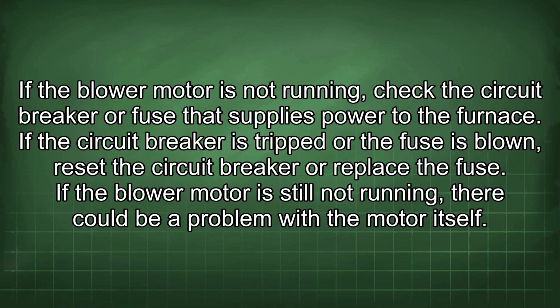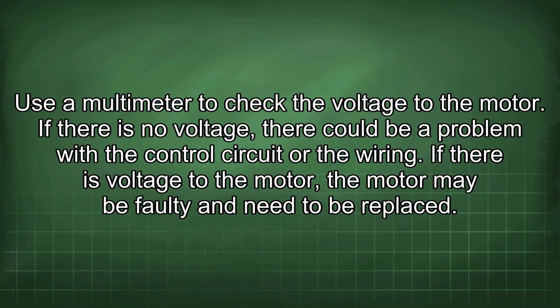If the blower motor is still not running, there could be a problem with the motor itself. Use a multimeter to check the voltage to the motor. If there is no voltage, there could be a problem with the control circuit or the wiring. If there is voltage, the motor may be faulty and need to be replaced.